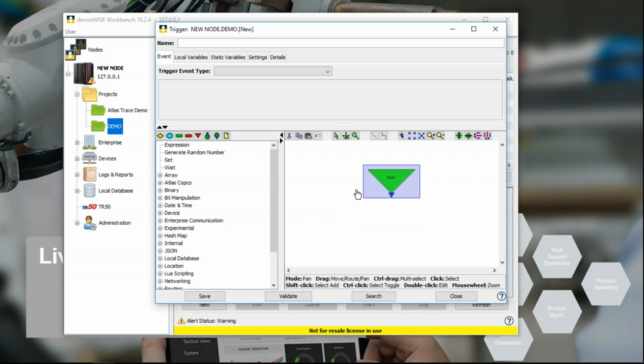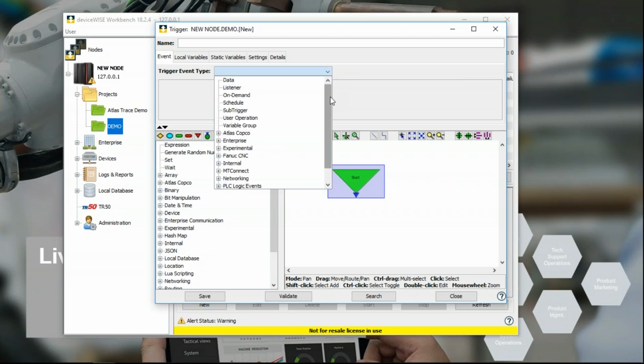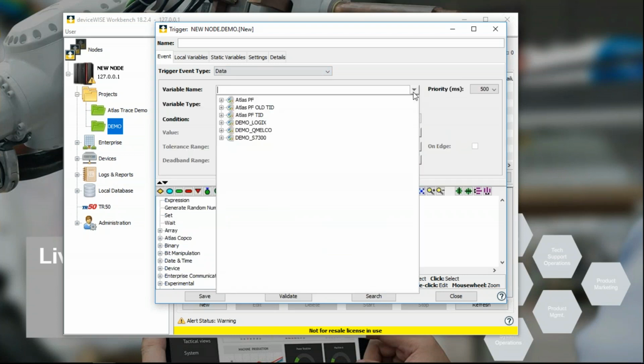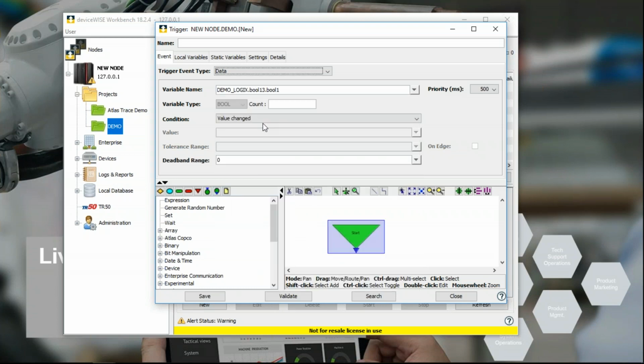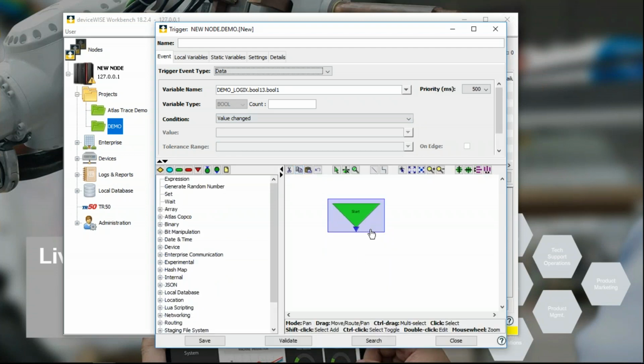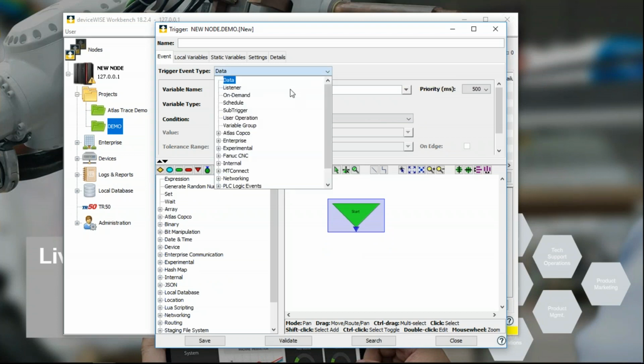There is no programming in the traditional sense. It's just drag and drop, fill in the blanks, and away we go. So for example, let's go back to the events. We have an event engine that is actually very powerful. There are many types of events. There is an event based on data, for example if a PLC variable changes. So if we pick this ControlLogix tag, what this event is saying is if this value changes, do something. This is what we're going to do in a little bit, down here. So this is what we call a data-driven or a data event.